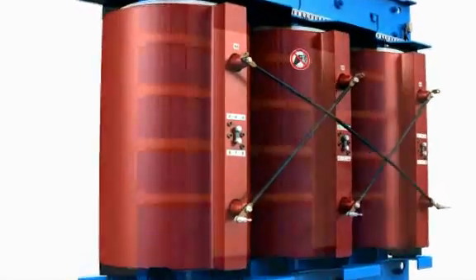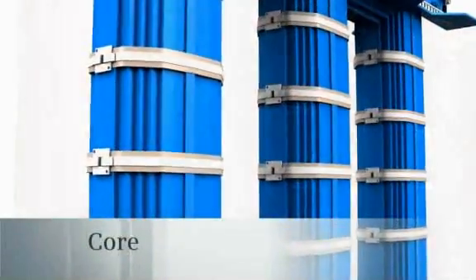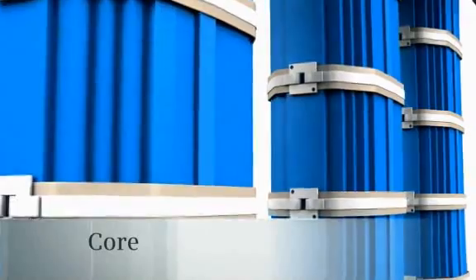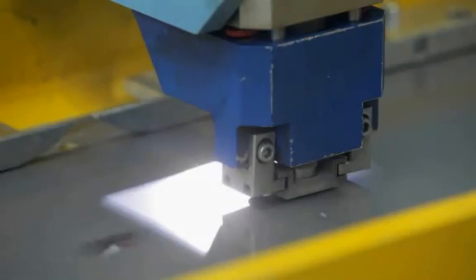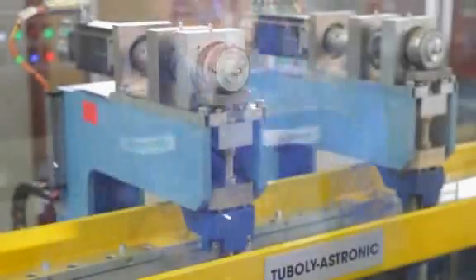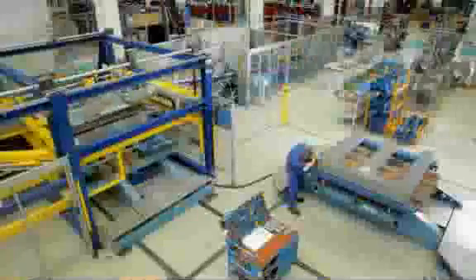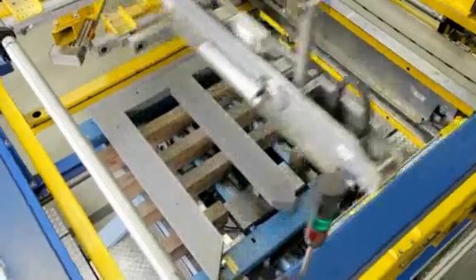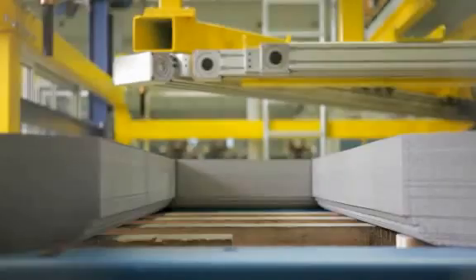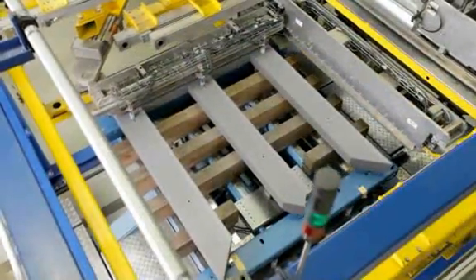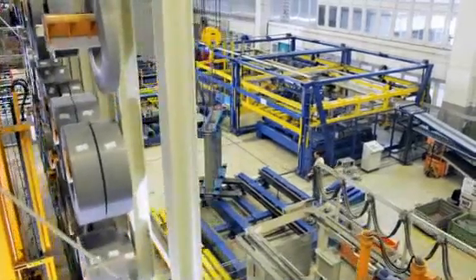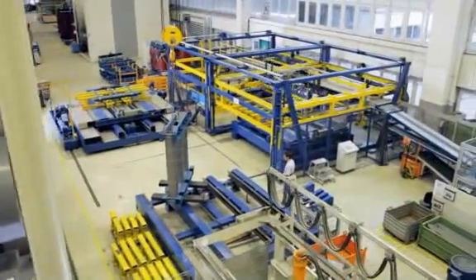To understand our definition of quality, you need to take a very close look at how we work. Take the iron core, for example. Ultra-thin electrical sheets are stacked one on top of the other. Right here, at the very beginning, precision already drives the process. Finest raw materials and most exact cuts guarantee that the transformer operates with the lowest noise and the highest efficiency. That's why we process the materials ourselves. Only the best technology available is good enough for us.